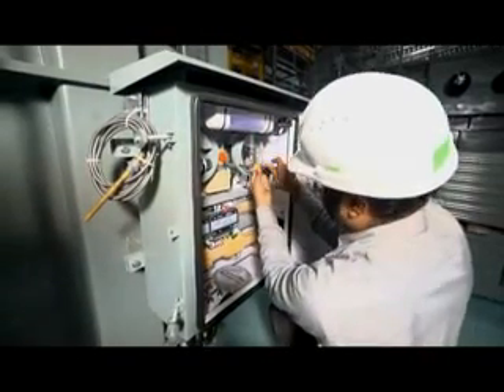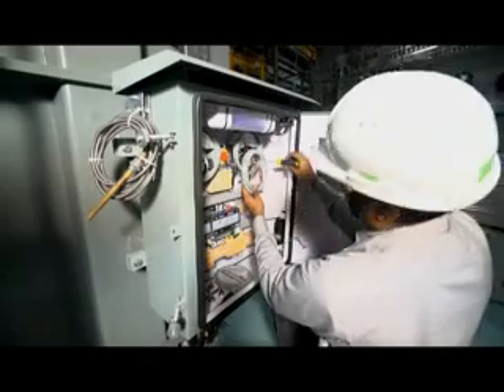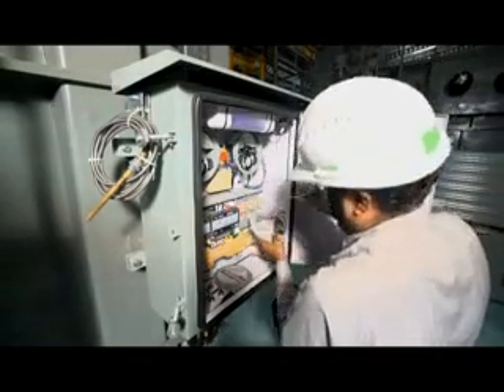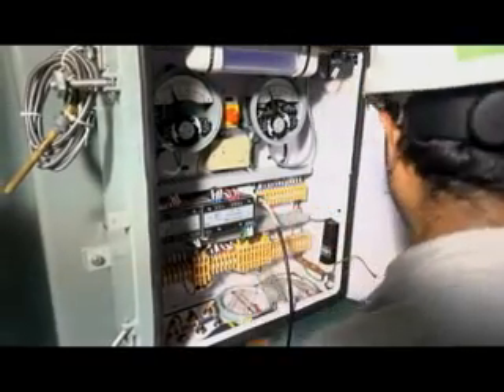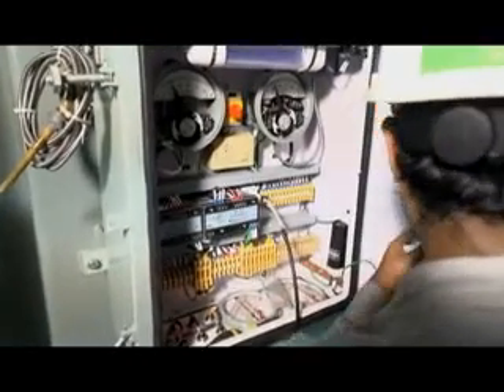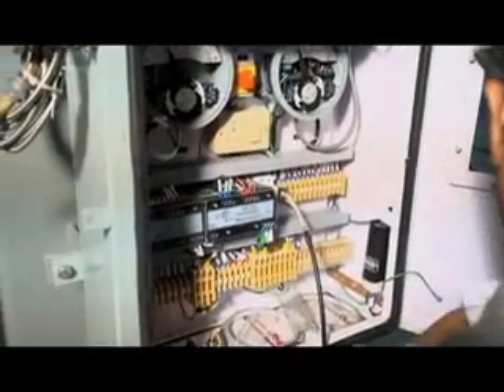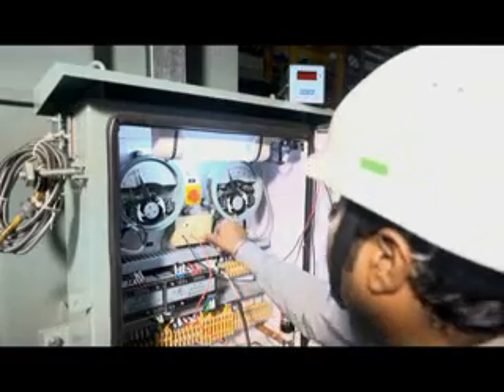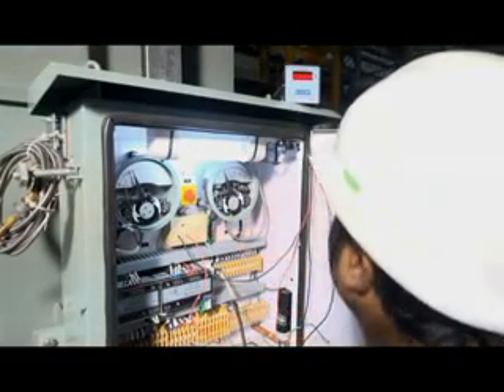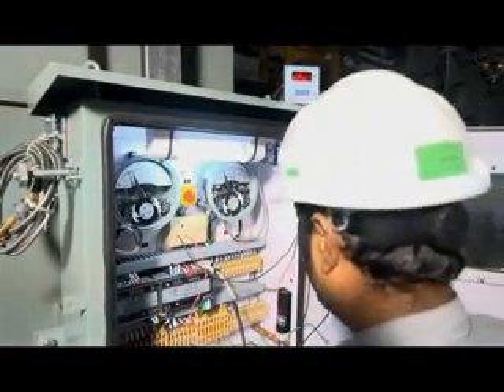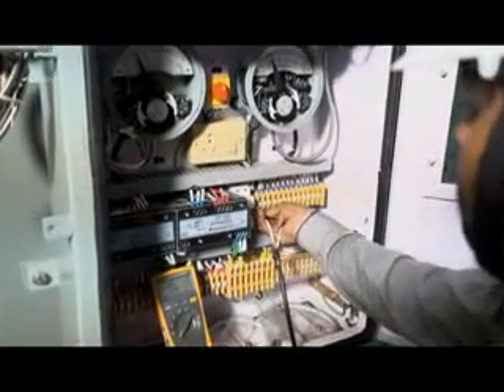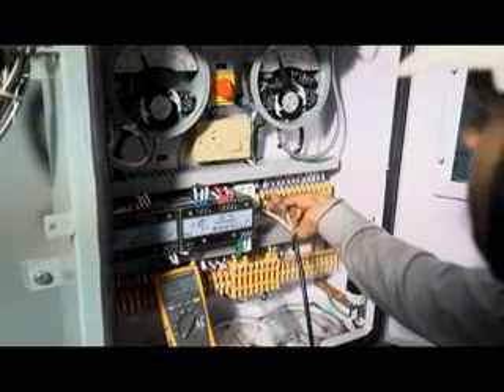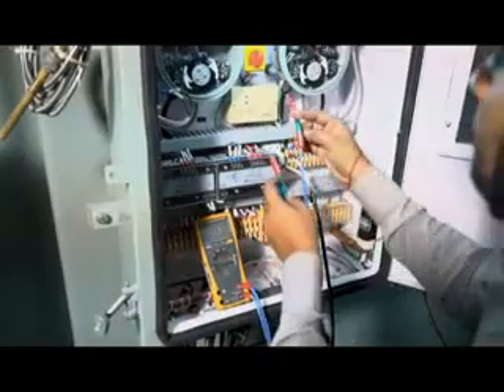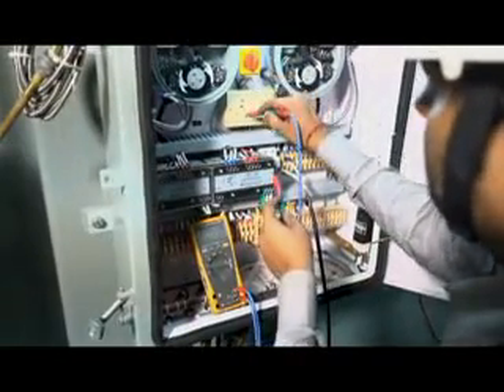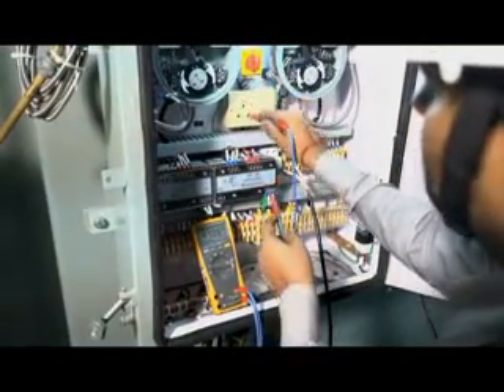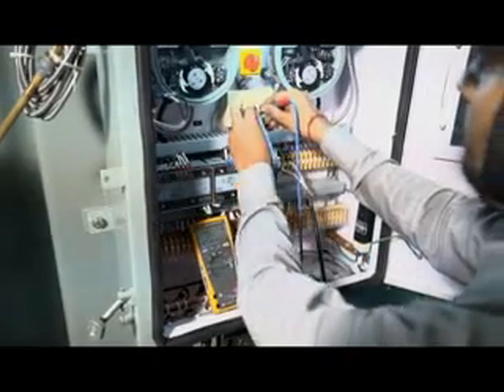In addition, all the secondary wiring of the transformer from current transformers, relays, oil level gauge, OTI, WTI, cooling fans, etc. are terminated on the terminal blocks, from which cables can be taken to the supply and control connections. The necessary control switches, contactors, etc. are housed in this cabinet. The cabinet may be provided with heating and anti-condensation facility. The cabinet has a ventilation facility which is protected against insect entry.